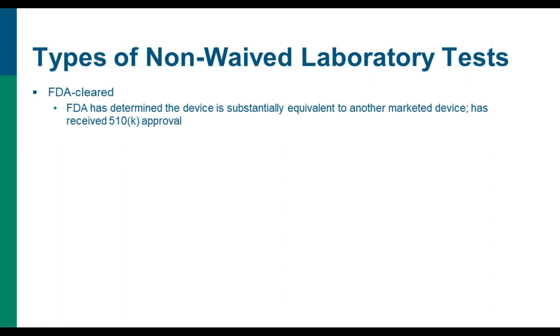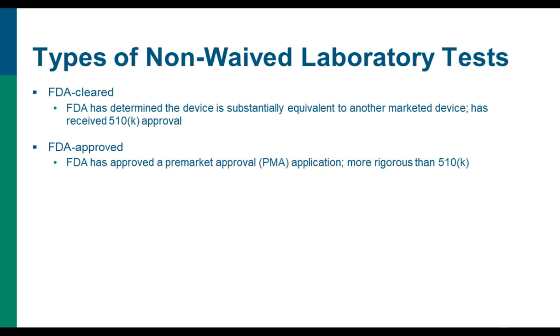So FDA cleared is a test that the FDA has determined is substantially equivalent to another already approved device or test, and so this is referred to as a 510(k) approval. There's also FDA approved, so often FDA cleared and FDA approved are used interchangeably, but they actually have slightly different definitions. So FDA approved is where it has received approval for a pre-market approval application. And this is a more rigorous application for the FDA than a 510(k).